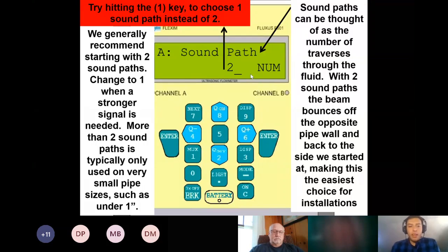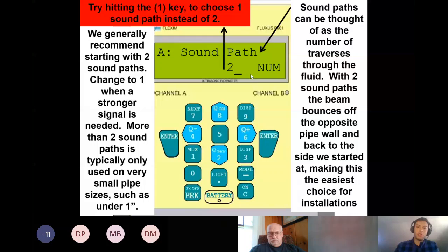Typically, if you start with a 2 sound path and you need more signal, we would go to a 1. But the more sound paths you have, it can also increase the accuracy, but it'll decrease your signal strength a little bit. So, like I said before, just start with 2, and you guys can take it from there.